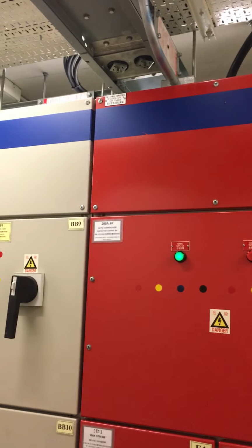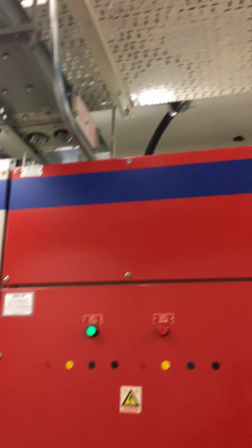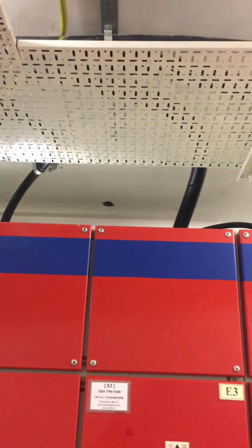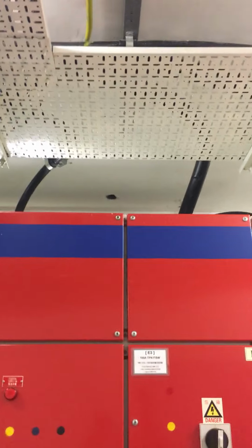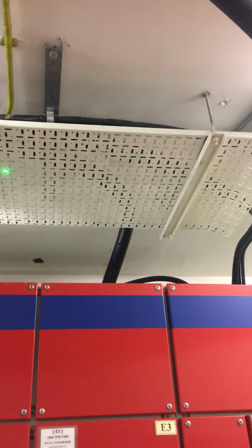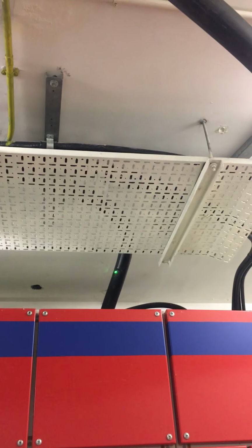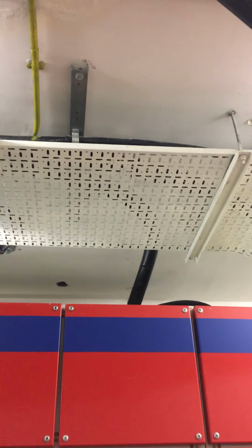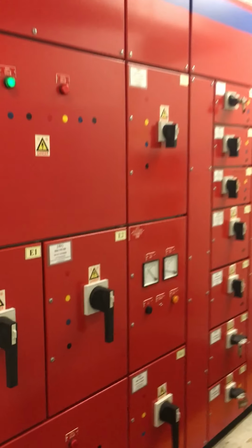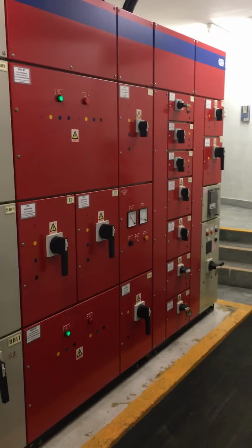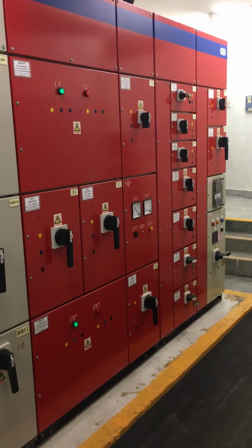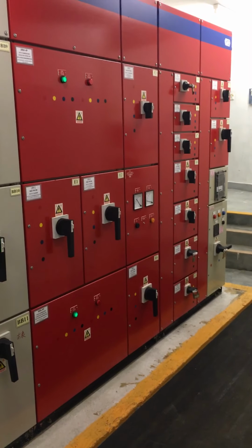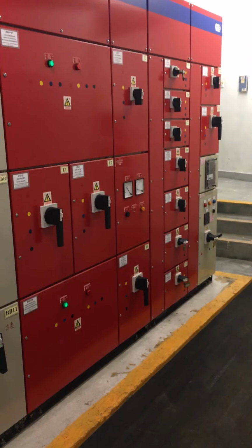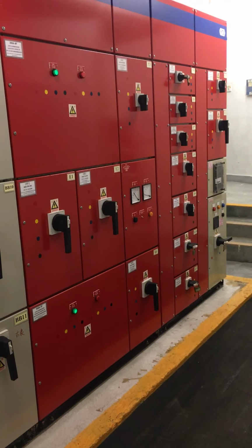Okay, so on the 9th floor, we have the generator, and in case of power outage, the generator will back up the essential loading. So that cable from the generator should be this one, if I remember it right. Okay, so this cable came from the generator on the 9th floor and supplied to this red switchboard. Okay, so you see the color is red because all the loading supplied from this switchboard are essential loading. Usually the fire services load, like the fire services pump, the FS lift, and the emergency lighting.